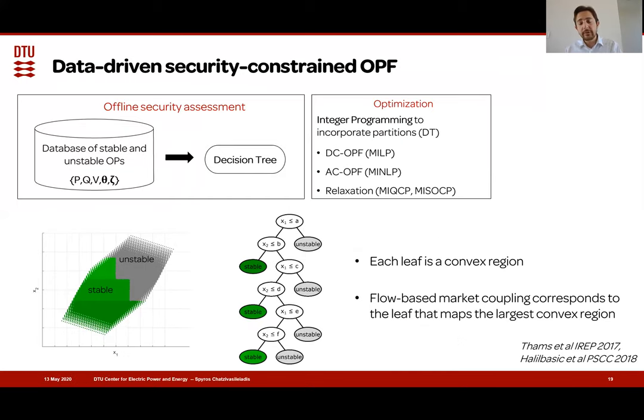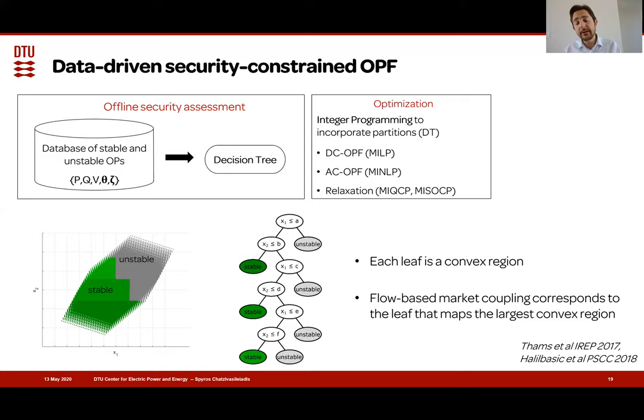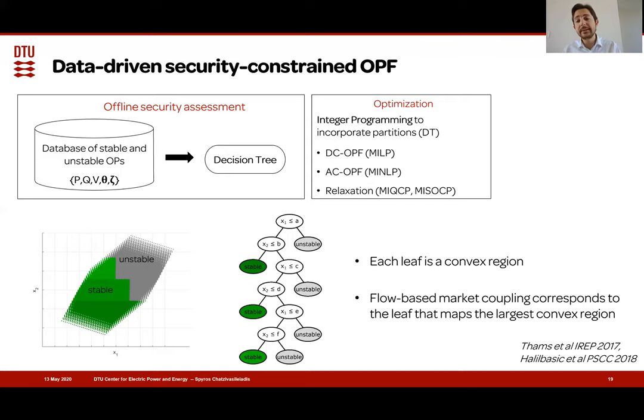We can solve a MILP if we're talking about a DC optimal power flow with linearized equality constraints. We should solve a mixed integer nonlinear program if the equality constraints are the original quadratic power flow equations, or we can also do a relaxation and convexify the problem to obtain a mixed integer second-order cone or quadratic convex formulation.